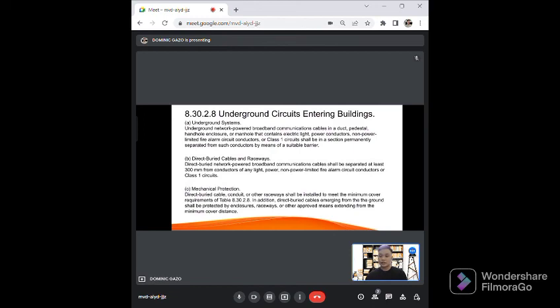And for mechanical protection from direct buried cable, we have minimum cover requirements. And this cable emerging from the ground shall be protected by enclosures, raceways, or other approved means extended from the minimum cover distance.